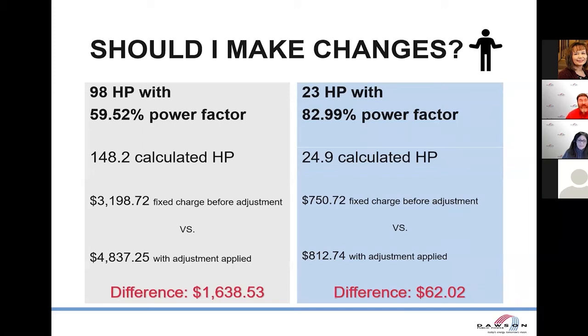So here's a couple examples. The guy on the left here has a 98 horsepower motor with about a 60% power factor, so he's clocking in at roughly 148 horsepower. You can see the two charges he gets there before and after the adjustment. This is an annual difference of $1,638. That's probably going to be worth it to put a new capacitor on and get that corrected.